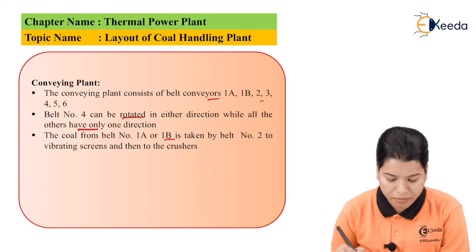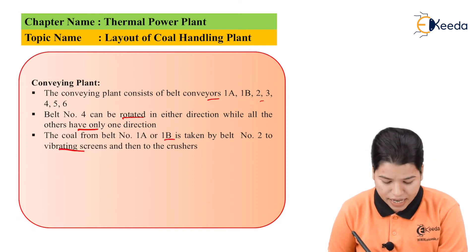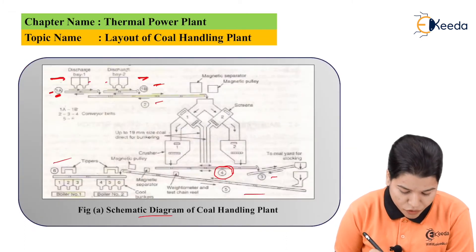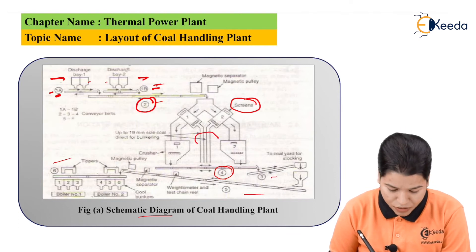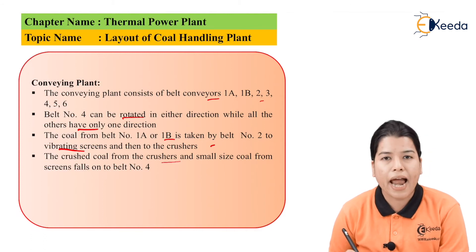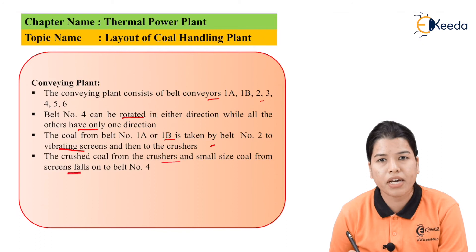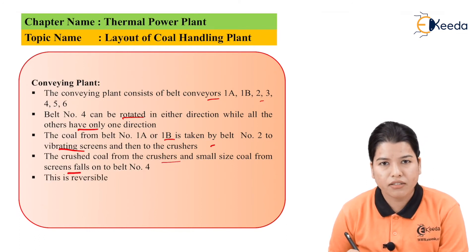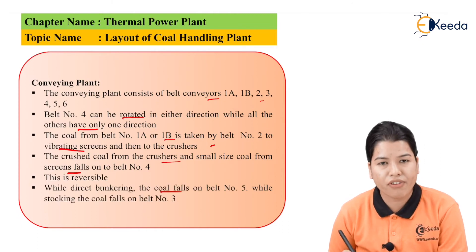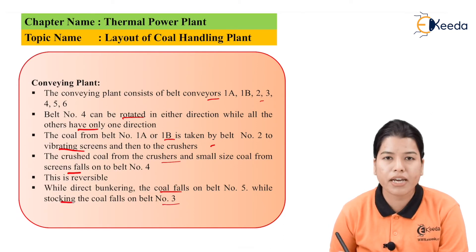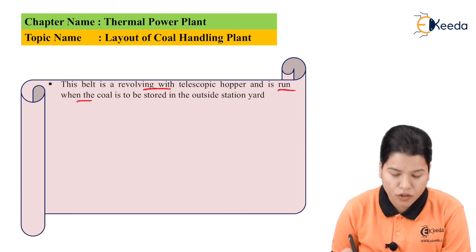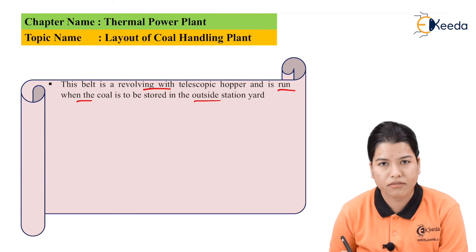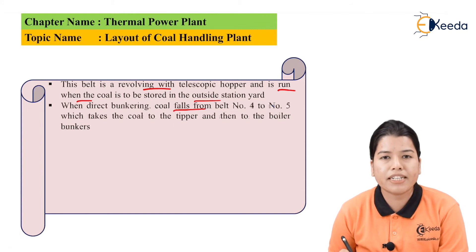The coal from belt number 1A or 1B is taken by belt number 2 to the vibrating screens and then to the crushers. As seen in the diagram, coal from belts 1A and 1B is given to belt number 2, then to the screens, and from the screens to the crushers. The crushed coal from the crusher and small-size coal from the screen fall on belt number 4. This process is reversible — with direct bunkering, the coal falls on belt number 5, while during stocking, the coal falls on belt number 3. With direct bunkering, coal falls from belt number 4 to belt number 5, which takes the coal to the tripper and then to the boiler bunkers.